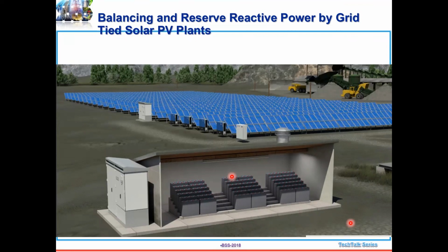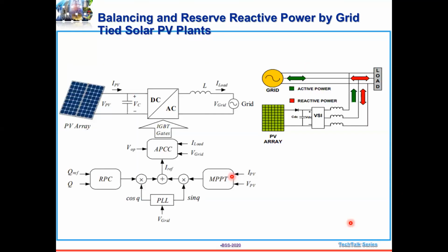This proved that the system is capable of providing reactive power support without any issue in the active output, without degrading it. Their main concern was that providing reactive support would degrade the active output. But the inverters were rated for 1.1 MVA, so they could give reactive support without degrading the active output. So now even the southern region is going for discussion with other inverter manufacturers and solar power persons to provide this reactive support from the inverter system.